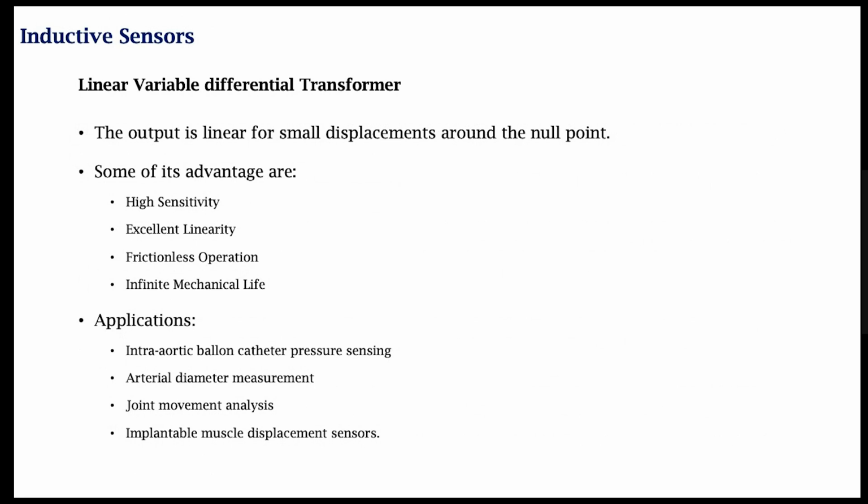So quite frequently it is used in intra-aortic balloon catheter pressure sensing. Quite often that is an application of the LVDTs. Another application is in measurement of arterial diameters.